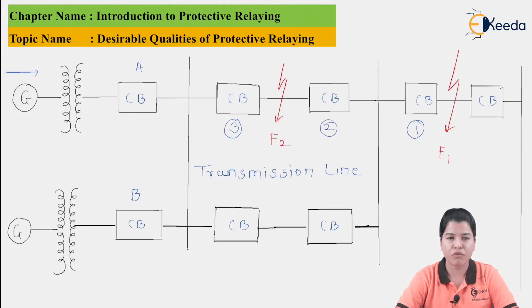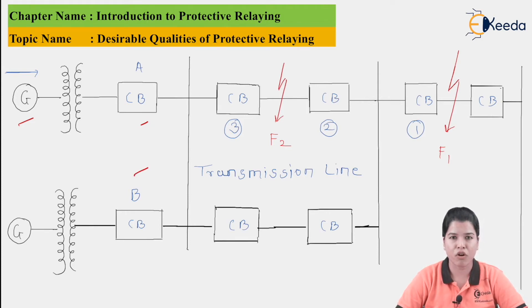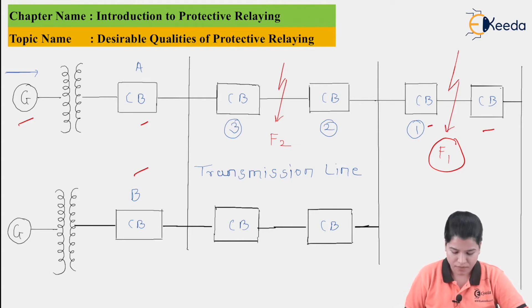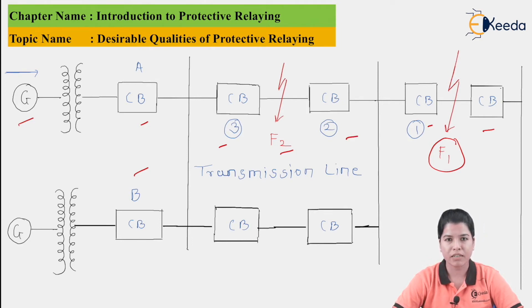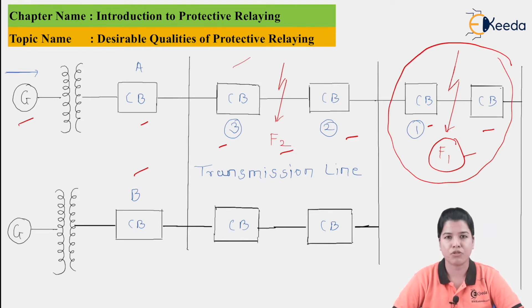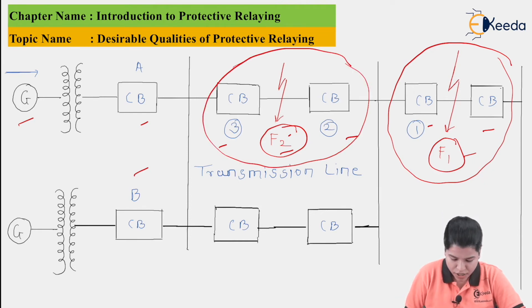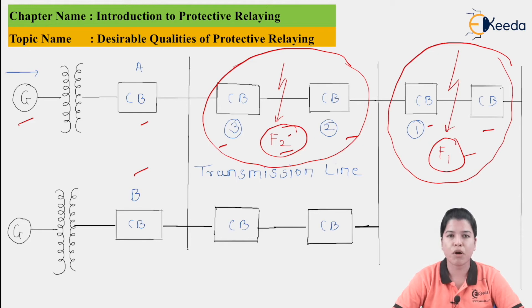A figure shows the protection system for a transmission line. The supply goes from the generator through Circuit Breaker A and Circuit Breaker B. Two faults are considered: Fault F1 occurring between these circuit breakers, and Fault F2. The protective relay should discriminate whether the fault has occurred in its own zone or a neighboring zone. If F1 occurs, the circuit breaker in that zone should operate — not the circuit breaker in the neighboring zone. Similarly, if F2 occurs, the circuit breaker in that zone should operate. This is proper selectivity and discrimination.